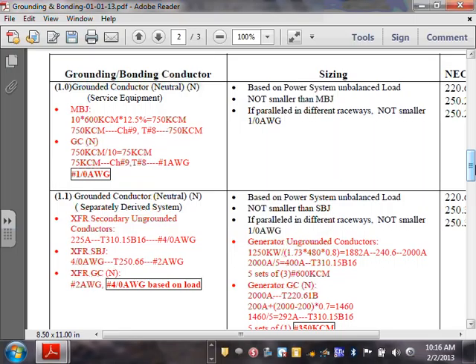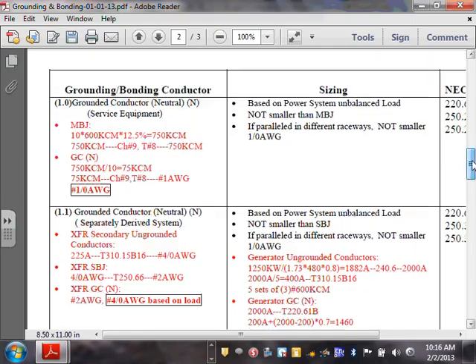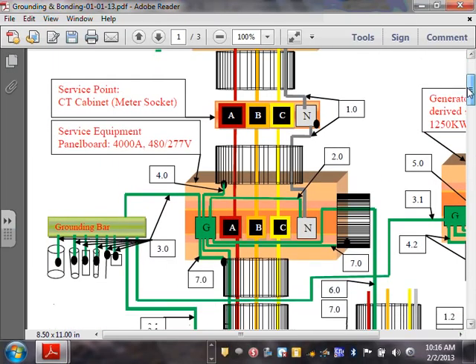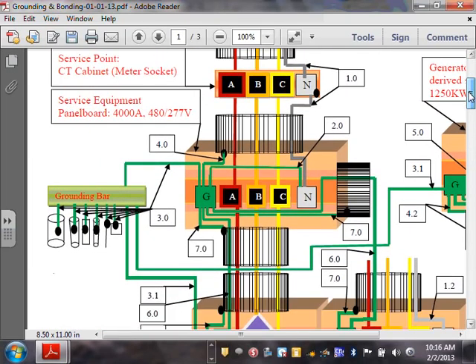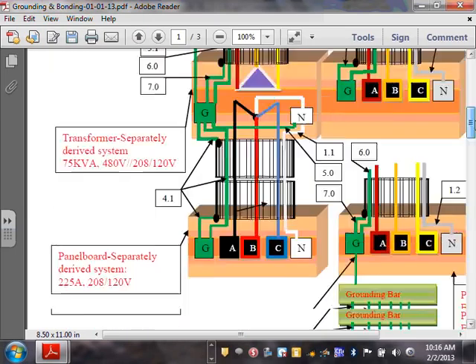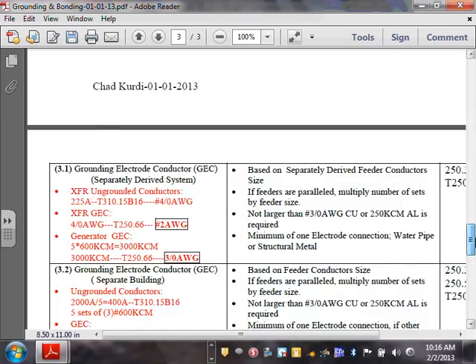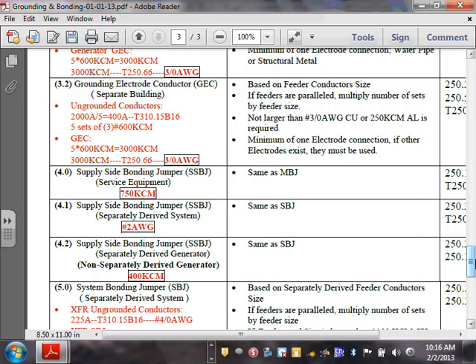Okay, so let's go to number 1. That's the grounded conductor. So what was the second one that I wanted to size? I'm going to go directly into it, and I'll give you guys a break in a second. Let me go to number 4. Can you guys see where number 4 is? That's the conduit, all the way to number 4. Okay, here's number 4. It says supply side bonding jumper. That's the name of it, supply side bonding jumper. That's when you take a piece of wire and you connect all the conduits coming to your service, daisy chain them, and bring them into the ground bar inside the switch.